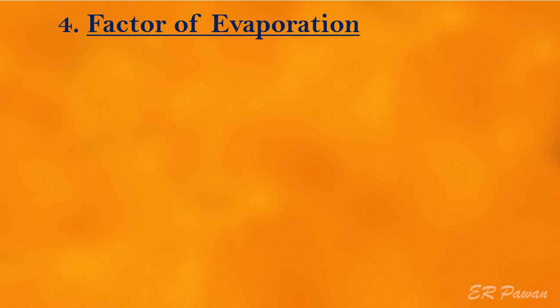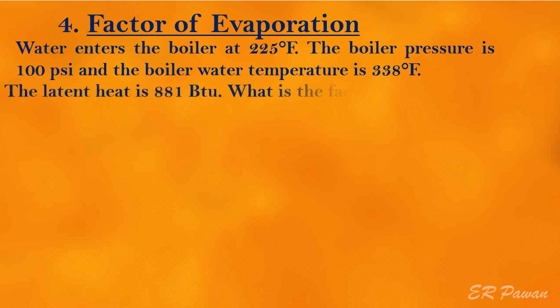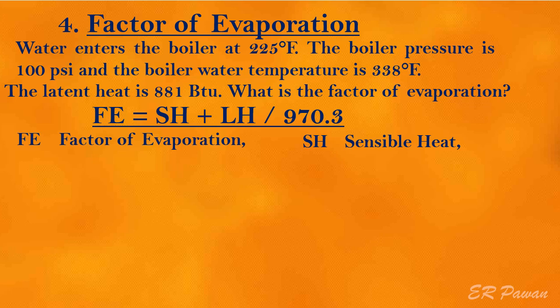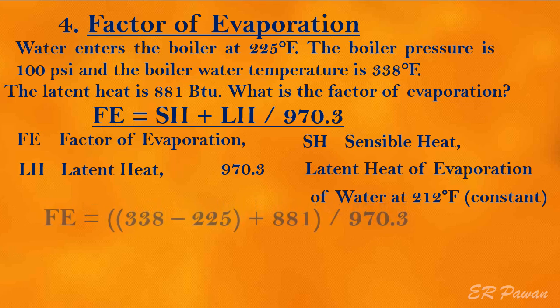Formula 4 — Factor of Evaporation. Water enters the boiler at 225 degrees Fahrenheit, the boiler pressure is 100 pounds per square inch, and the boiler water temperature is 338 degrees Fahrenheit. The latent heat is 881 BTUs. What is the factor of evaporation? FE equals (SH + LH) divided by 970.3. Where FE = factor of evaporation, SH = sensible heat, LH = latent heat, and 970.3 = latent heat of evaporation of water at 212°F (constant). Let's put the value in the formula.